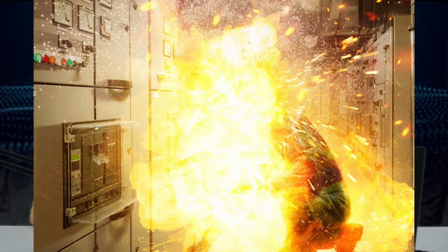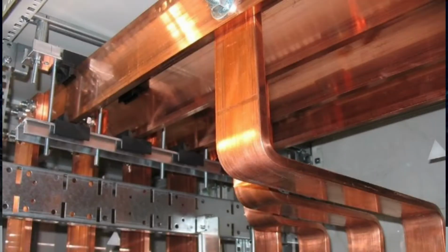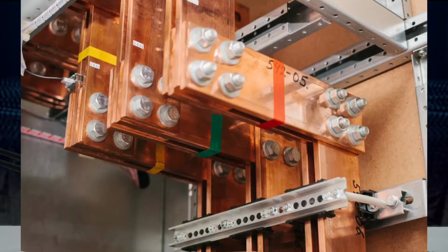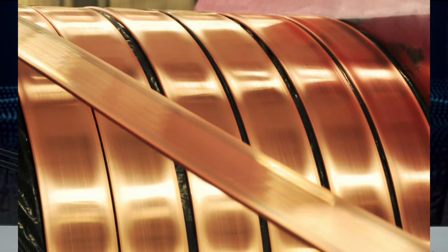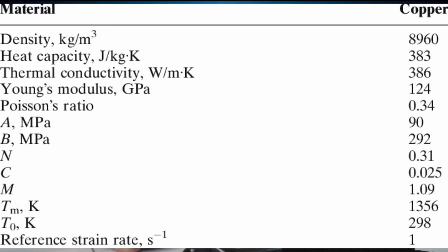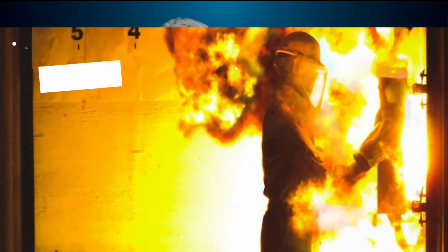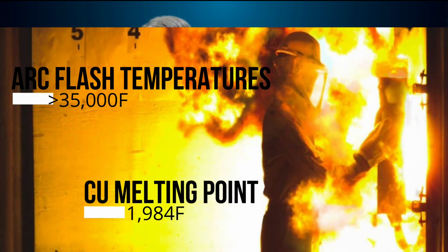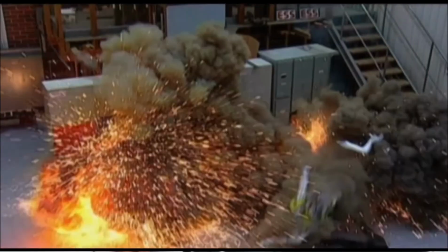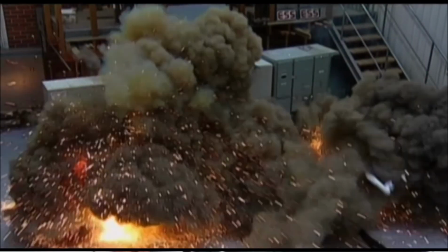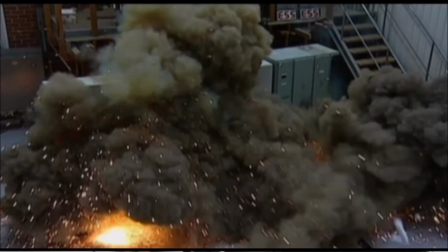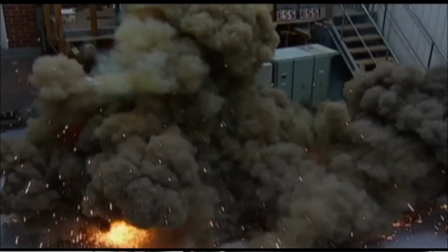Molten metal. Molten metal is generally from the liquefying of the bus material that is used within electrical equipment cabinets. Copper is generally the preferred choice of metal when it comes to electrical bus material. Copper bus is a soft, malleable, ductile metal with very high thermal and electrical conductivity. With arc flash temperatures exceeding 35,000 degrees Fahrenheit and copper's melting point at 1,984 degrees Fahrenheit, the copper doesn't stand a chance in that amount of heat. Spraying droplets of molten metal exceeding speeds of 700 miles per hour can easily penetrate standard PPE, or personal protective equipment. This leaves the employee severely exposed to this particular hazard.